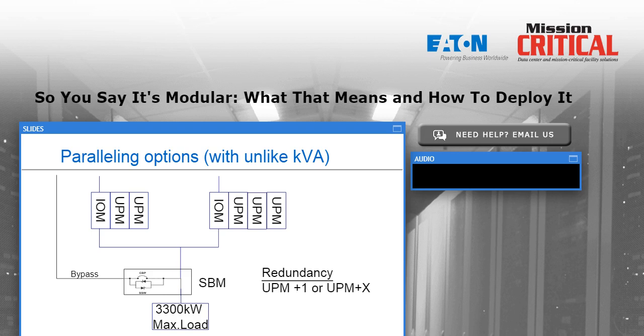Now, suppose as we get a little more complicated here, I want to parallel UPSs and I end up with unlike kVA ratings. Traditionally, we've basically said, hey, if you want to parallel UPSs, you need to parallel them all the same size, cookie cutter. Well, nowadays, that's definitely not necessary with a modular UPS. Let's suppose the customer has a long-range plan of 3.3 megawatts or 3,300 kilowatts, which shows at the bottom of the slide. But they don't need that on day one. They don't need anywhere close to that much capacity on day one. So they install a 600 kilowatt UPS over here on the left with 2 UPMs, and that's all they need maybe for the first several years of operation. So time passes, the system functions as expected, and all of a sudden something unexpected happens.